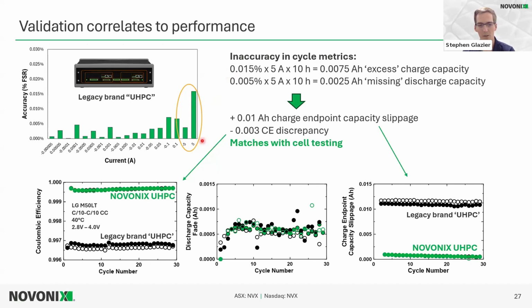So this direction in charging was actually overcounting in current, which we were able to benchmark. The discharge was undercounting. For simplicity, we showed this all as absolute values, but it was actually undercounting the discharge current. And when we back-of-the-envelope calculate what we should see in cycling metrics, we would expect about 10 milliamp hours of excess or mismatch in the charge and discharge capacities, which leads to this offset in a metric called charge endpoint capacity slippage, which when we actually tested identical cells on the two systems, we saw almost exactly that difference.